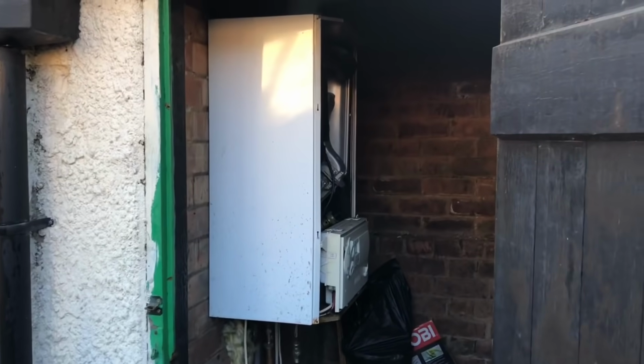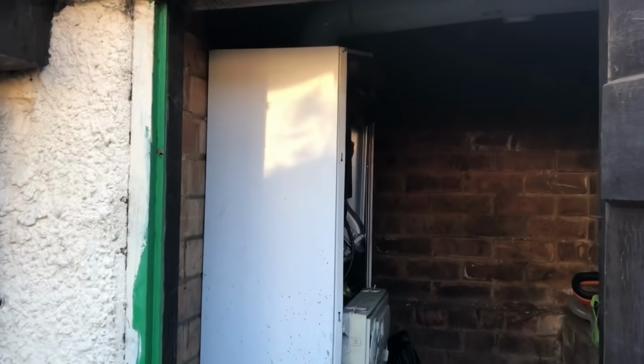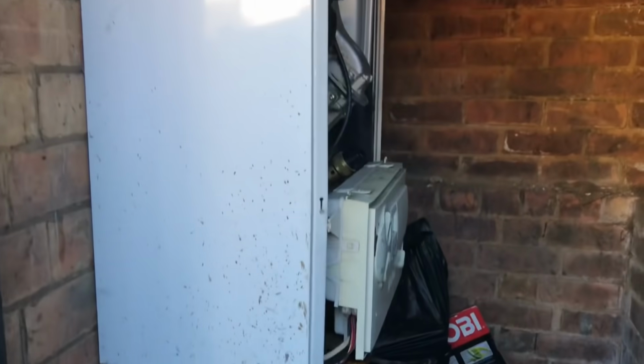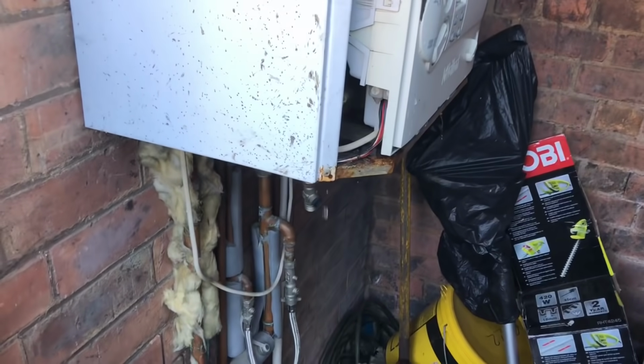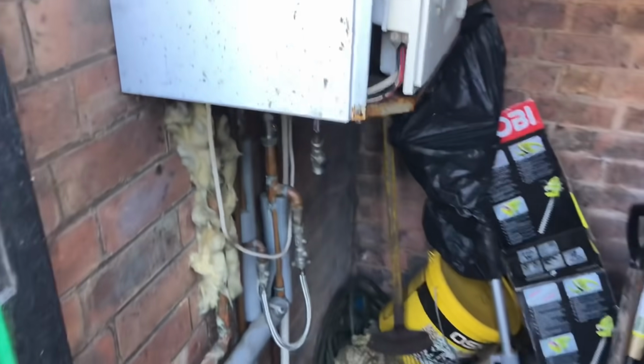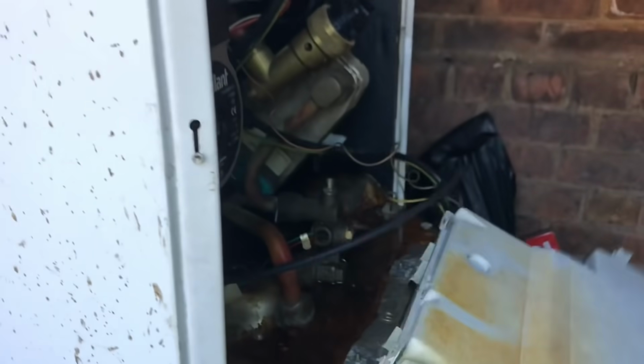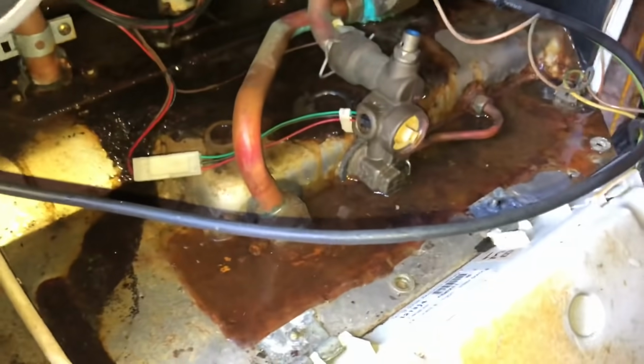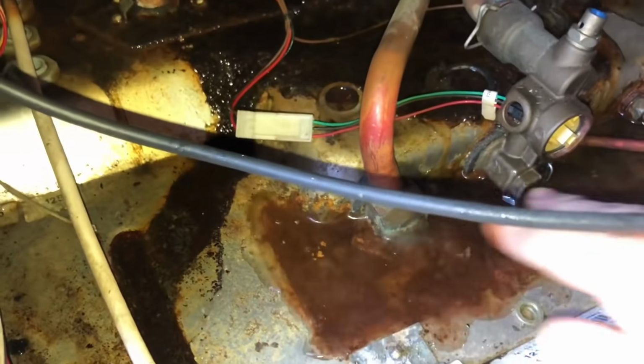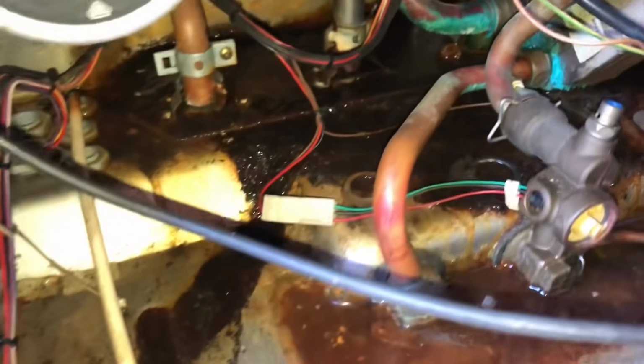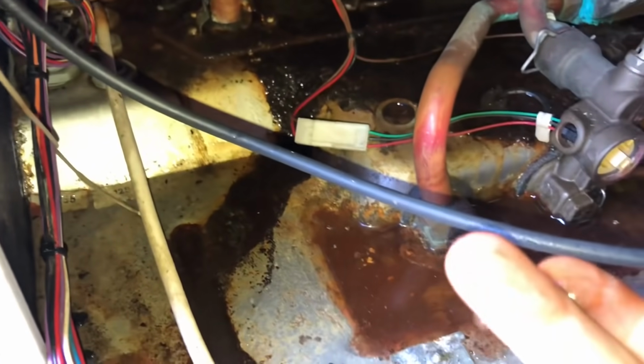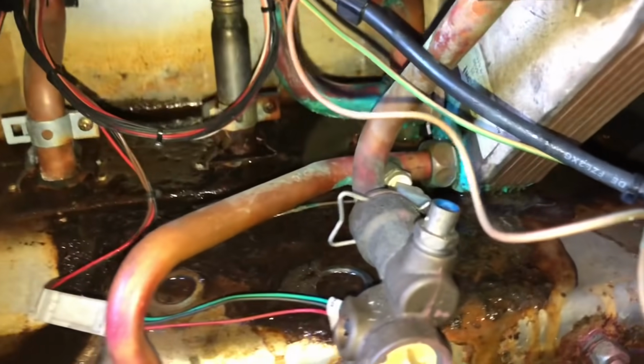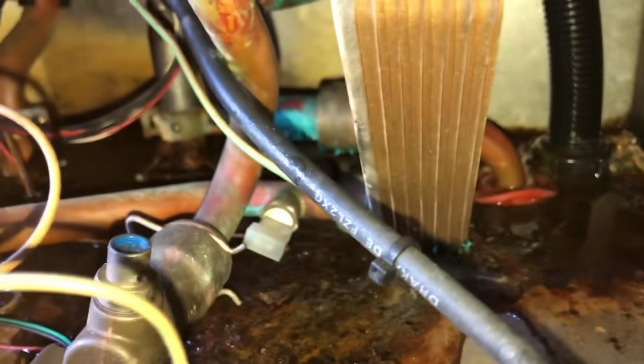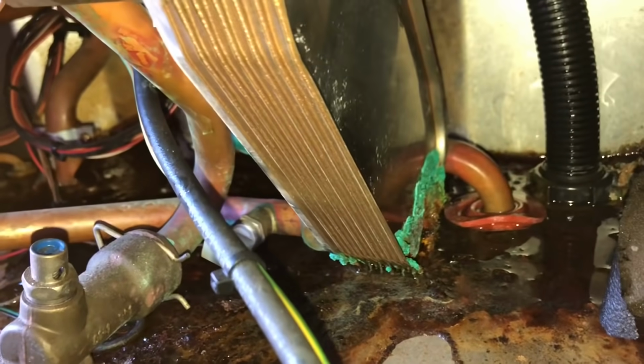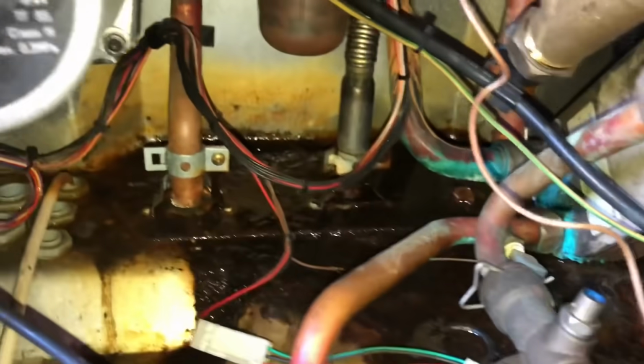Right, been called out to this boiler by the letting agency because they've not had any heating or water over the weekend. And they said the boiler was making a noise and leaking, so you can see there's water dripping out of it. I have had a quick look at this, took the cover off. So, you can see on the inside here, it's swimming with water, and the amount of rust and stuff tells me that it's been leaking for a while. And if you look on the plate there, and at the side of the plate, if you can see it, it almost looks like it's got a hole in it.